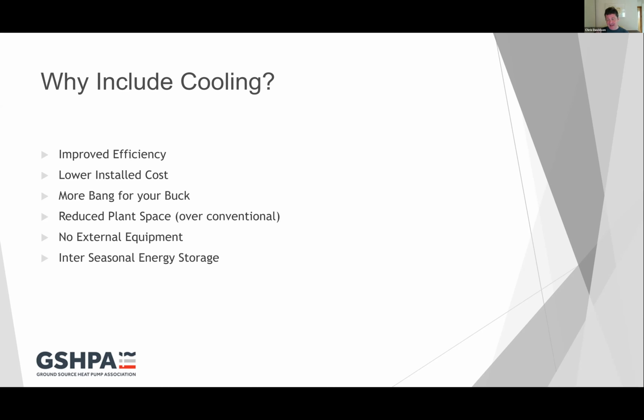What I'm talking about today is primarily borehole systems, but the same applies to horizontal systems, though not exactly. The physics of horizontal arrays, being much closer to the surface, is slightly different to borehole arrays. For example, when designing a horizontal system we need weather data, whereas for a borehole system it's practically nothing more than the average ground temperature throughout the year. Put succinctly, a horizontal system will not store heat as effectively as a borehole system does. So those are the reasons why we like to include cooling in any ground source system.